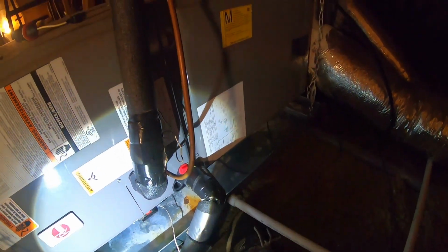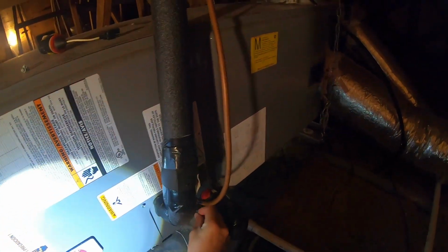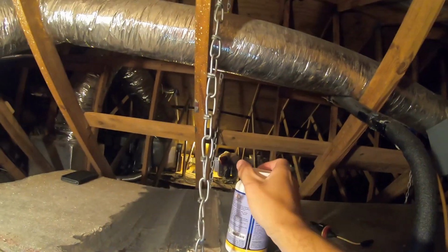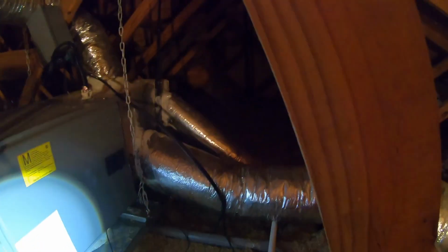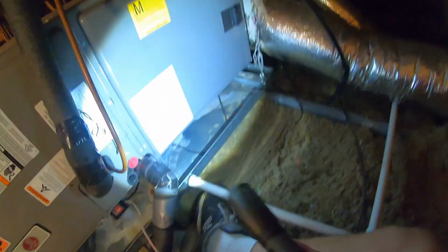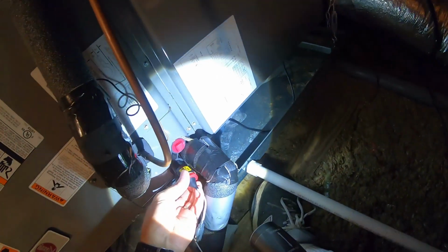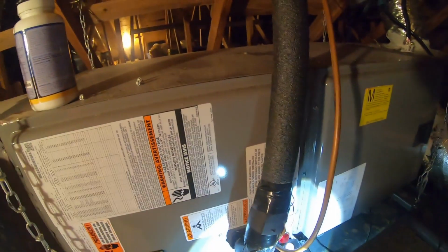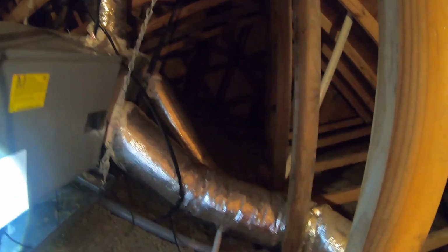Might get them to upgrade that one over there to a 3-ton. Some of you are probably saying, hey, wait, that air handler is a 3-ton. Okay, yeah, but the outdoor unit's a 2.5-ton. So they are a match set, but still a 2.5-ton unit. It has 2.5 tons of cooling power.